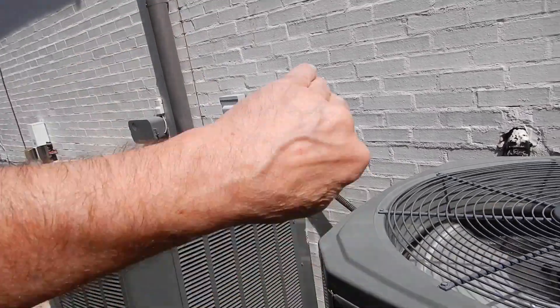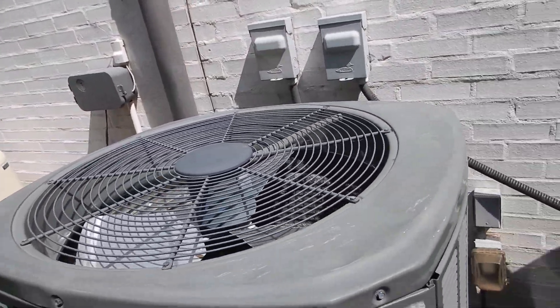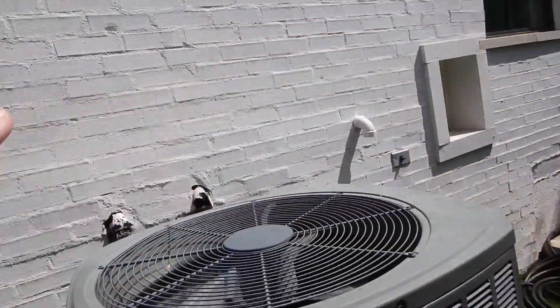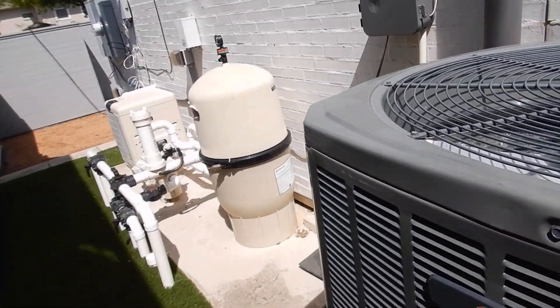The disconnects are not supposed to be located behind the units. They should be sealed on three sides to help prevent moisture from getting inside the wall system. I opened up all three of these and took still images to verify they are wired up correctly — and I confirmed that.